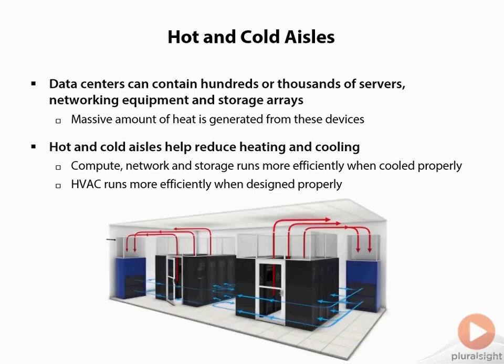Instead of simply placing equipment wherever it fits, it's much more beneficial to set it up in a fashion that takes advantage of hot and cold aisles and maximizes our HVAC. The basic concept is to place the front of the systems on either side facing each other so that cool air can be drawn into that aisle. The opposing aisles go back to back, so heat blows out the back of those systems — those become the hot aisles. The HVAC pulls that heat out, recycles it, filters it, and maintains a very clean atmosphere.